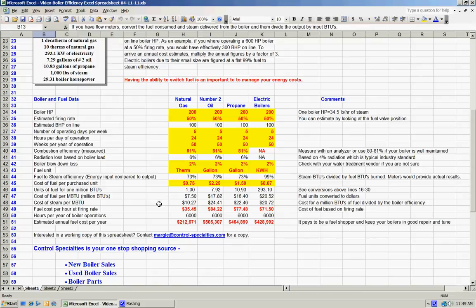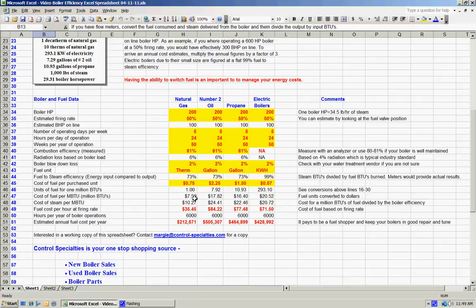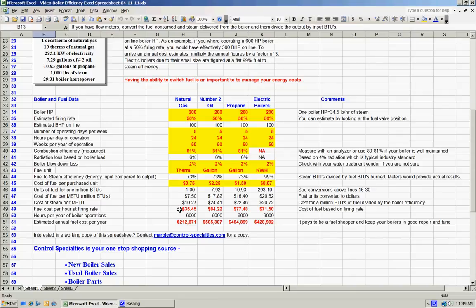Line 48 is taking the cost per million BTUs and dividing that by the fuel efficiency. So, in the case of a natural gas boiler, we take a fuel cost of $7.50 per million BTUs, a forecasted efficiency of 73%. If you do that math, you wind up with $10.27. The rest is just math dropping down from the data we punched in up above to get at the annual cost per year.